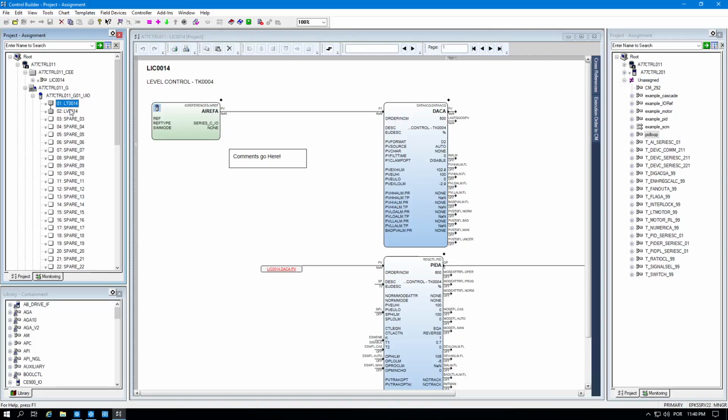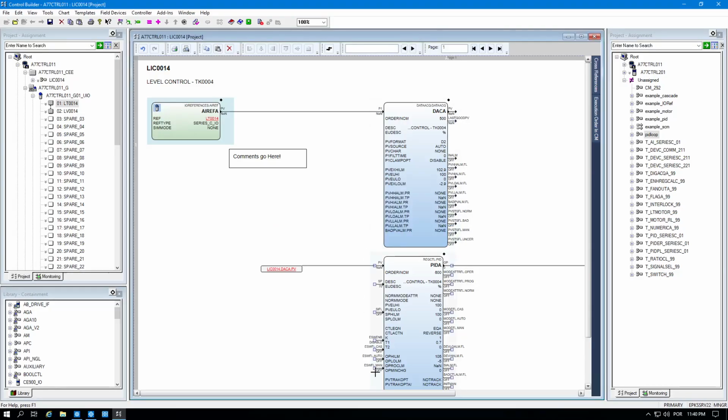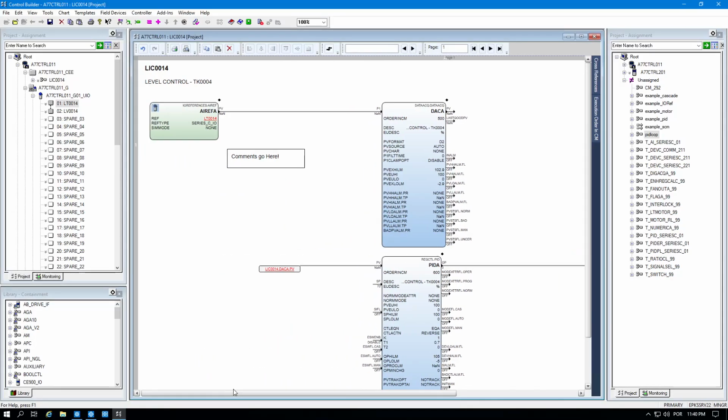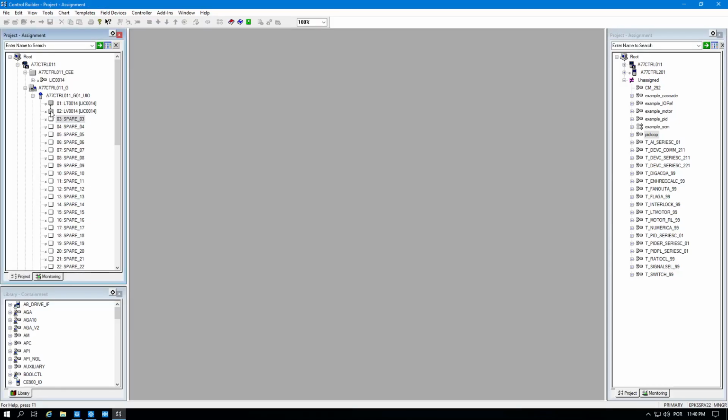After creating the tag in the channels we want, we will associate these channels to the logic of the PID that we just created. So, for the analog input it will be LT0014. And for the analog output it will be LV0014. Once this channel assignment is done, we can save, close, and we can load the logic.